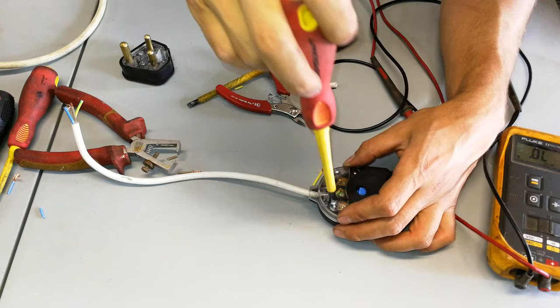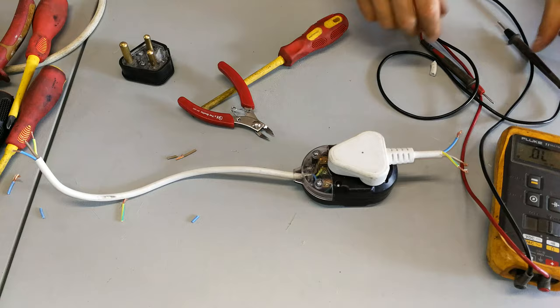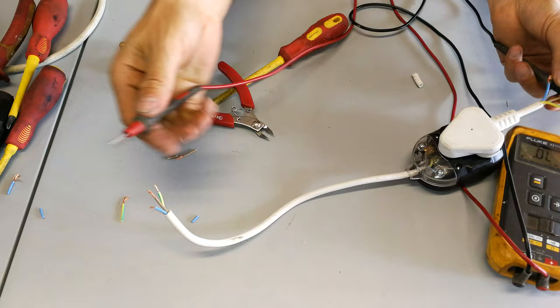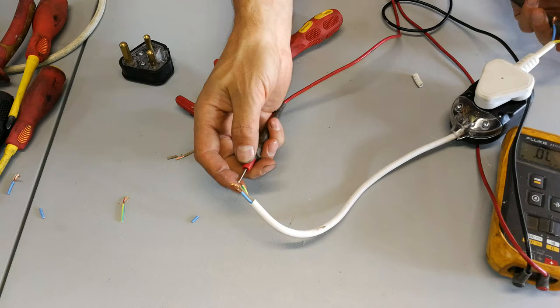So there you go. There's the colors on this particular one. Now I'm just going to test this to show you how it would be. There is the Janus coupler now wired up. I'm going to put my little test plug on there. And I'm going to show you there is the live. And then there's the extension cord. And there is the live. So we can see it's working fine. The other ones should have no conductivity. And then if I test the neutral, you'll see there's the neutral. And then the earth is over there.